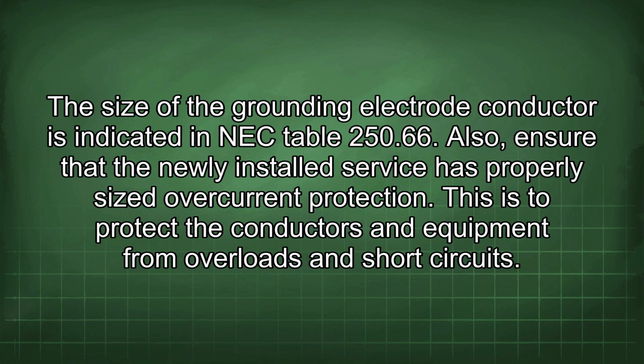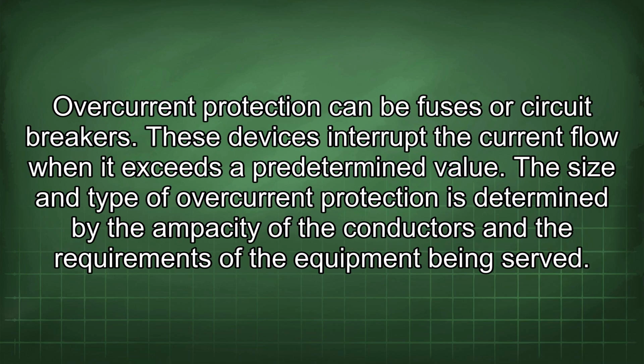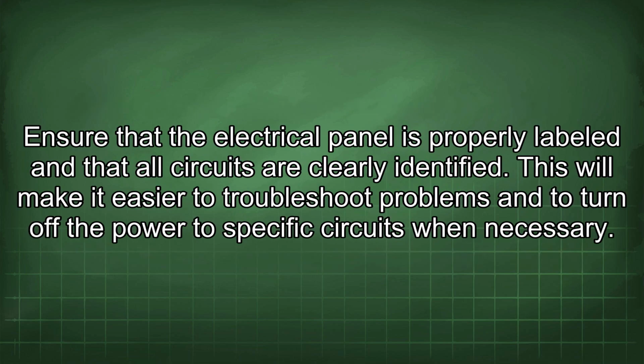This is to protect the conductors and equipment from overloads and short circuits. Overcurrent protection can be fuses or circuit breakers. These devices interrupt the current flow when it exceeds a predetermined value. The size and type of overcurrent protection is determined by the ampacity of the conductors and the requirements of the equipment being served. Ensure that the electrical panel is properly labeled and that all circuits are clearly identified.